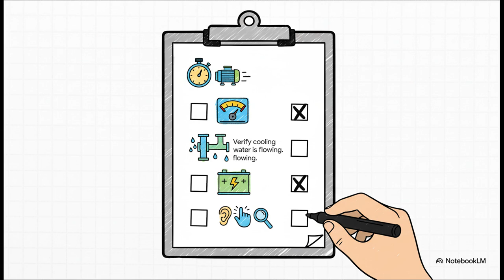So what does that weekly training actually look like? Well, for a diesel pump, the engine runs for a full 30 minutes. That gets it up to operating temperature and burns off any moisture that could cause problems. A technician goes through a super detailed checklist, checking fuel levels, making sure cooling water is flowing, listening for any weird noises or vibrations. It's a complete physical, every 7 days, no exceptions.